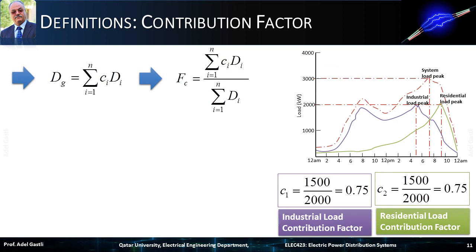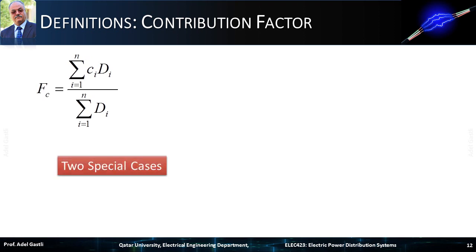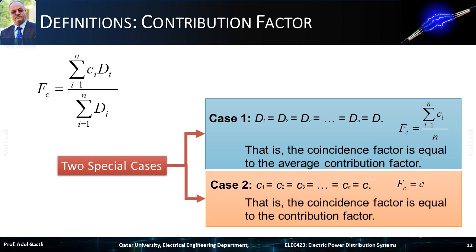Considering the previous example, the coincidence factor can be calculated based on this equation, and we obtain the same value calculated previously using the diversity factor equation. Using the coincidence factor as a function of class contribution factors, two special cases can be considered. In case 1, if all demands are equal, the coincidence factor equals the average contribution factor. In case 2, if all contribution factors are equal, the coincidence factor equals the contribution factor.